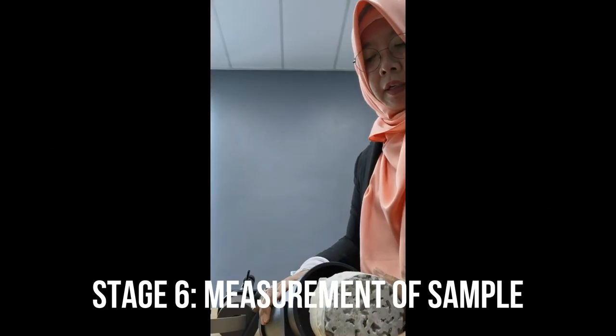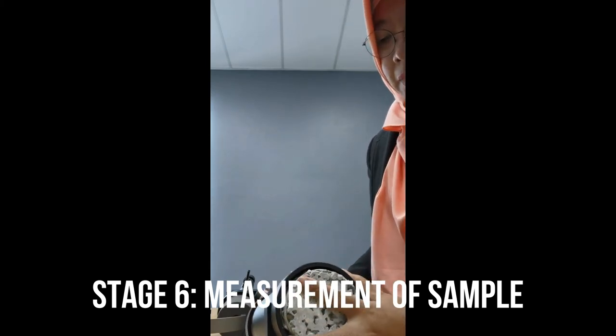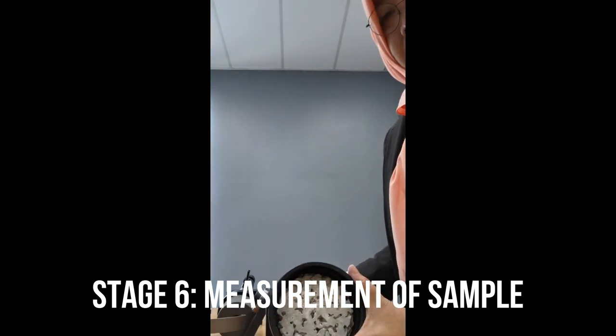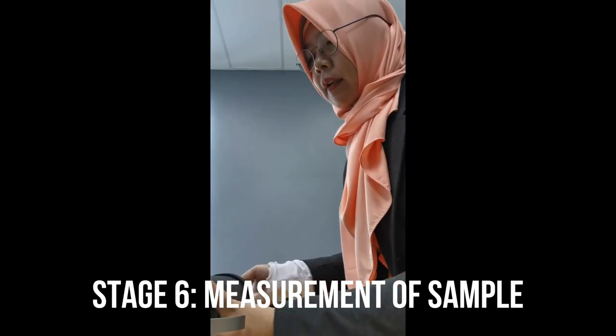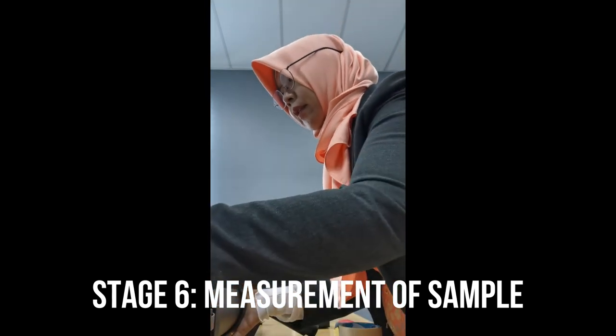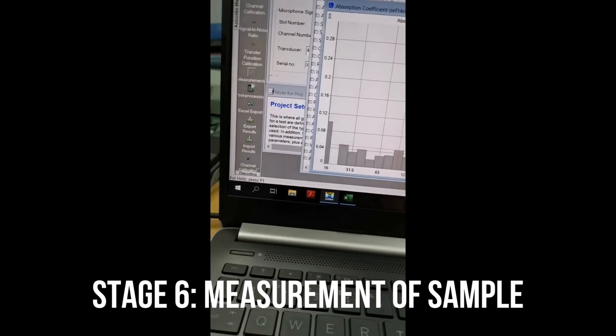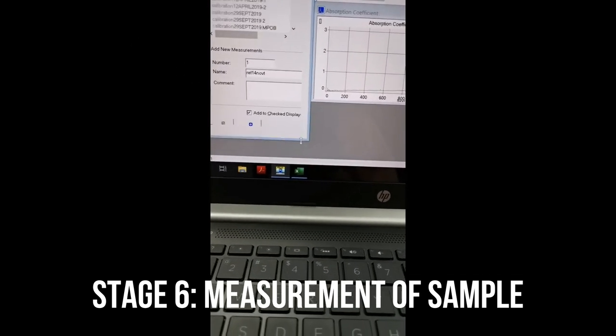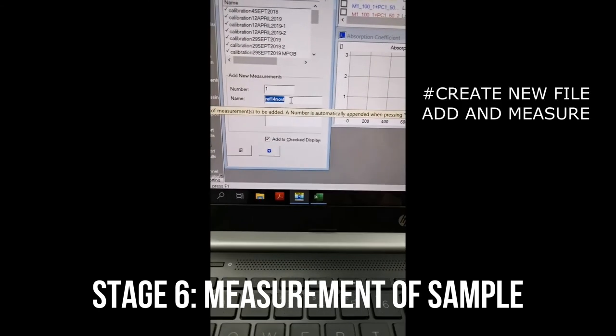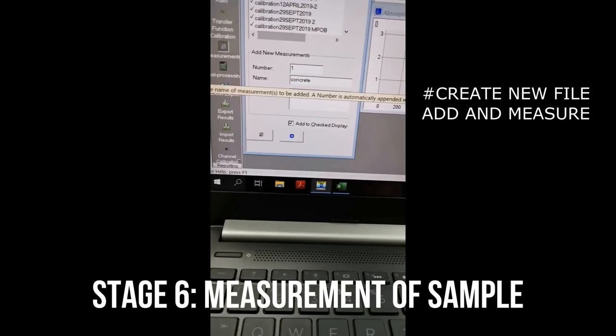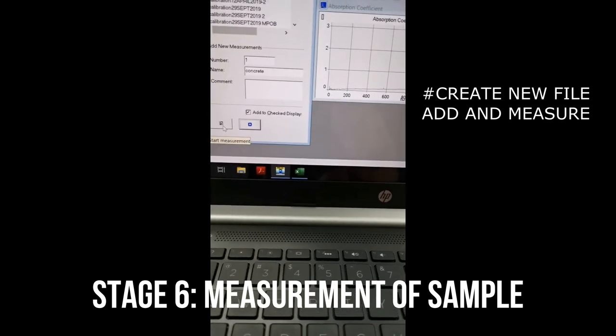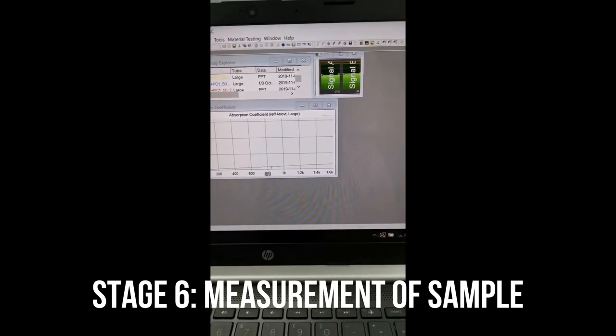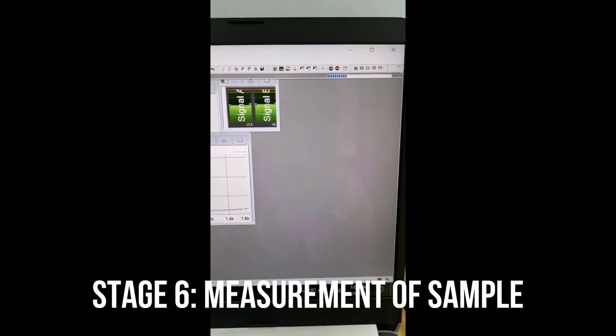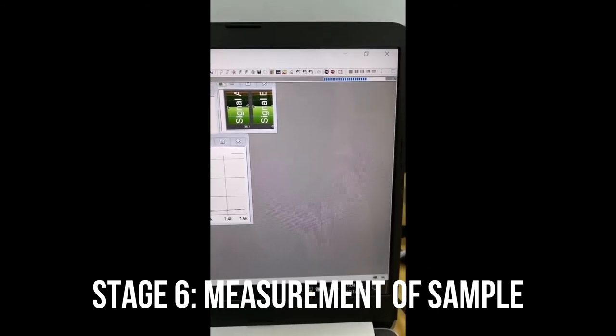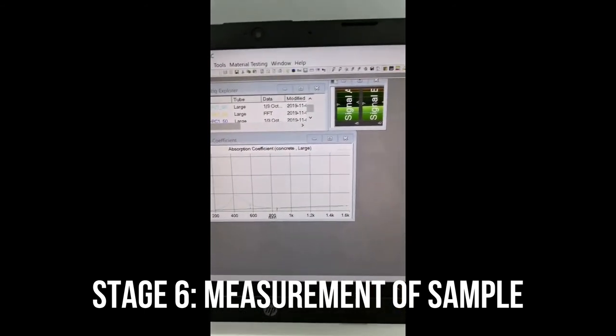So we have a sample here, a concrete sample, porous concrete sample. So insert it in the impedance tube, then put it here. Click the measurement. Okay, create a new file here. Say concrete. Okay, then add and press for the measurement. Okay.